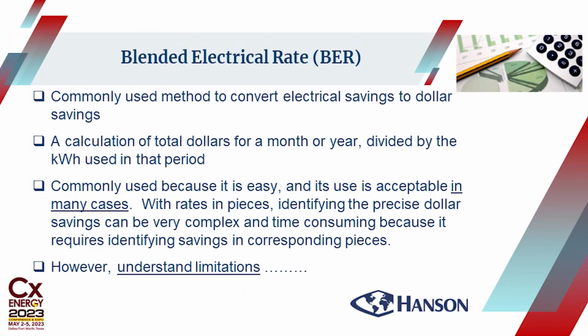Let's talk about blended electrical rate, something we touched on earlier today. A lot of engineers use a blended electrical rate when evaluating energy conservation measures. Instead of identifying specifically what the demand savings or consumption savings is, they come up with a blended rate based on annual use, and use that one unit cost to calculate anticipated or projected savings. It's commonly used and may be acceptable in a lot of cases, but not always—we're going to show you that and talk about the limitations.